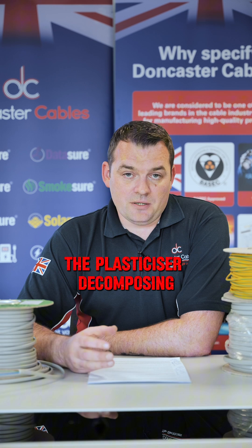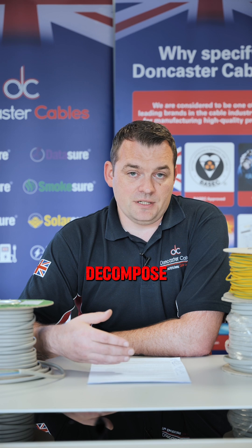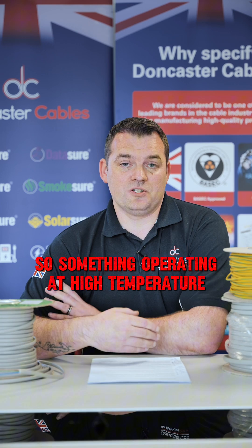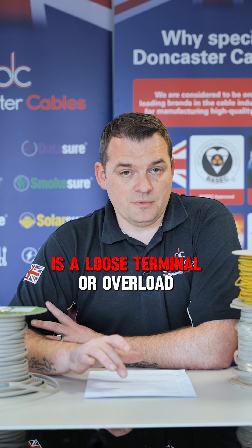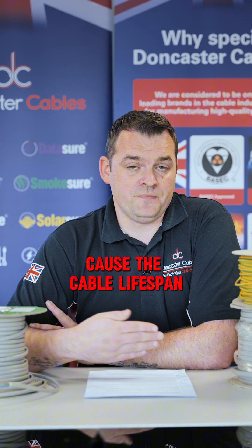The plasticiser decomposing also happens naturally in every PVC compound. Over time the plasticiser will decompose. Things that can accelerate that are high temperatures - something operating at a high temperature will cause that breakdown to happen faster. Two key things in installation practice are a loose terminal or overload in that circuit. Those are the two main things where higher temperatures will cause the cable lifespan to decrease.